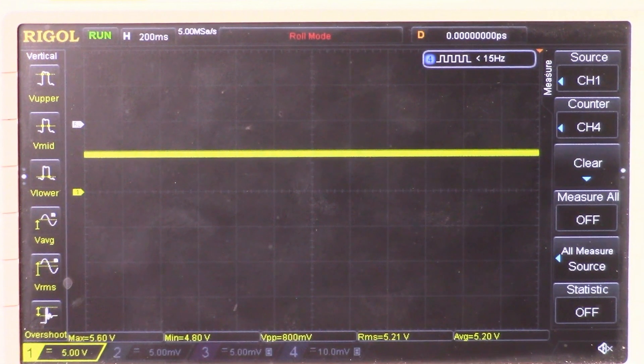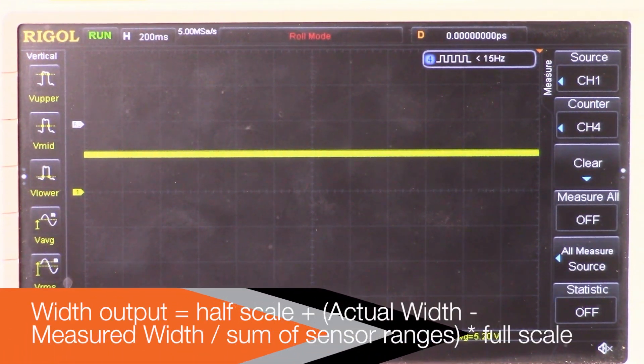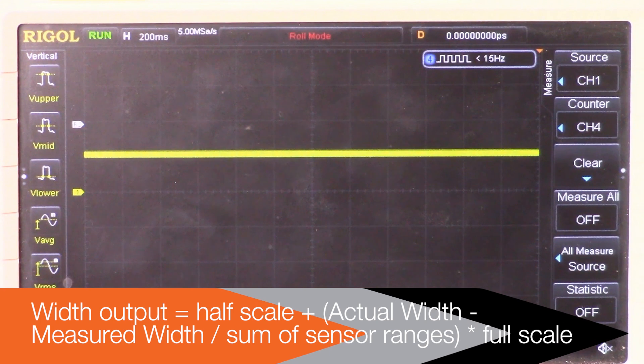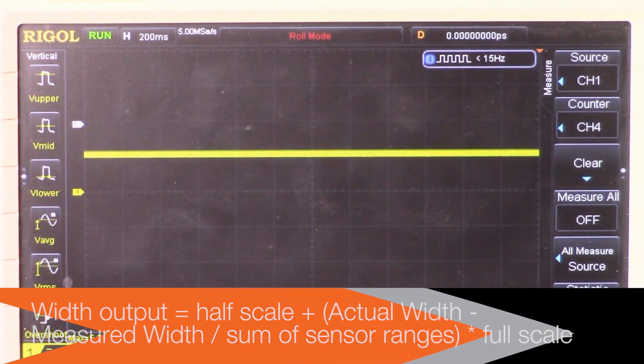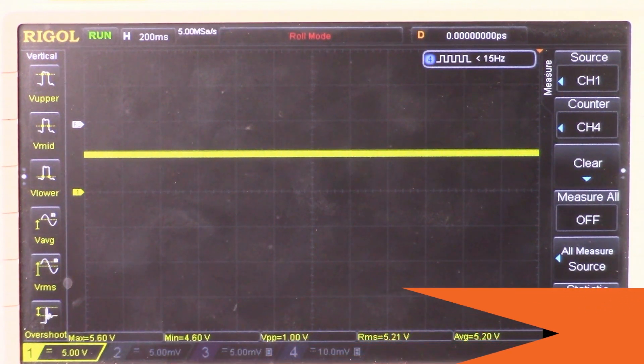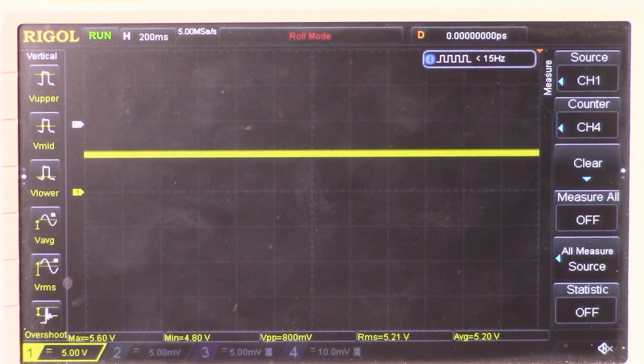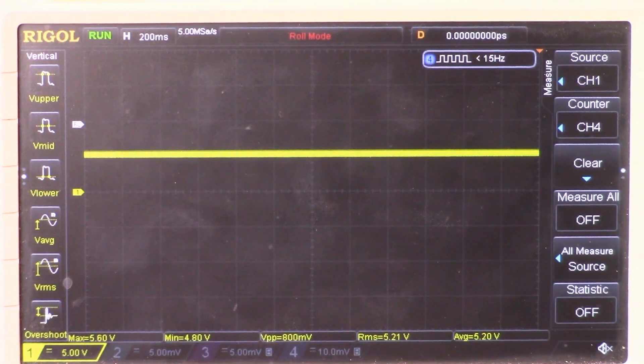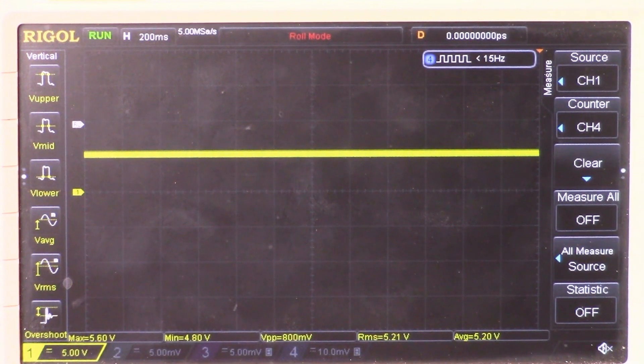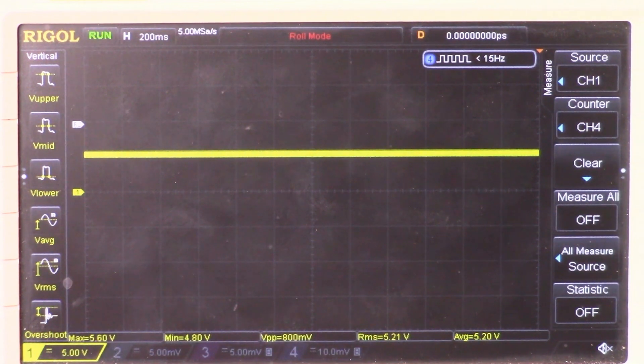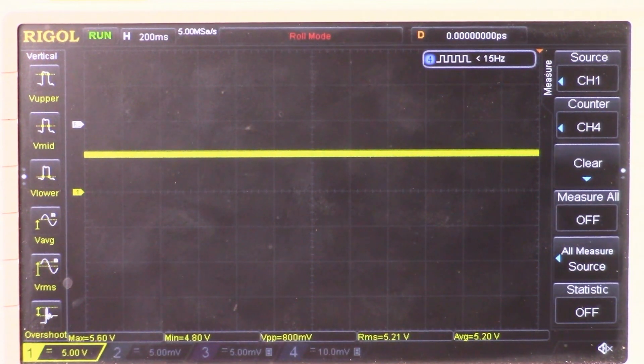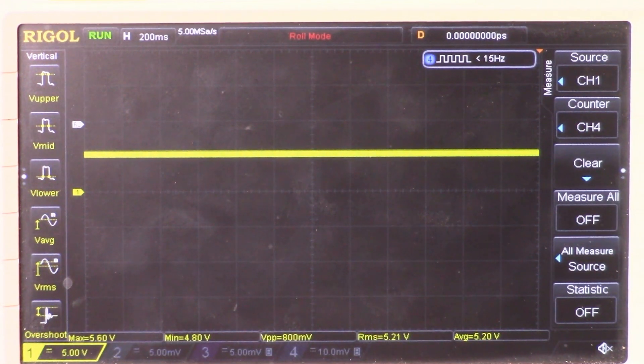Again, the way in which we compute this output is going to be whatever the error value is. Let's say we have the error as 1 inches or 1 inch, and then the output is going to be 5 plus whatever that 1 inch corresponds to with respect to the sensors that are used. So if we have two 4 inch sensors, then the error output, 1 inch, is going to be 1 divided by the sum of the two sensor ranges, let's say 4 inches each, so that's 8 inches. So that's 1 eighth times the output range.